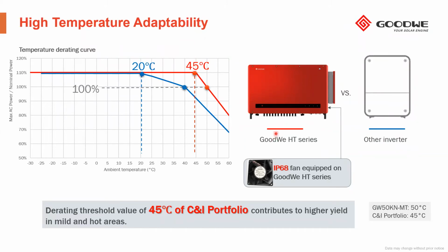Let me give you an example. If we get a high current moment in the input, because there is a very good irradiance moment, the inverter could eventually be overheated. So the inverter will apply this algorithm to reduce the output power. That means that it will reduce the input of the inverter. The limit depends on the inverter manufacturer, depends on the design. In our case, for the C&I portfolio, the threshold is 45 Celsius degrees ambient temperature.